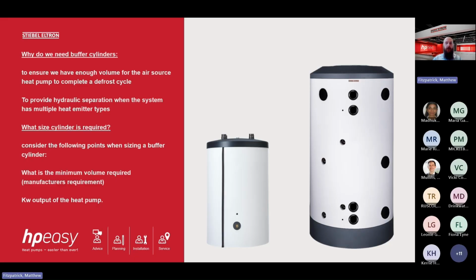So in the heart of winter, when it's very cold and very humid and the air source heat pump is extracting the energy from the air, it can pull the intake air exceptionally low to 0, -1 temperatures, which means any water droplets on the evaporator can freeze, and the heat pump runs in reverse to thaw out the evaporator. If we do not or cannot achieve sufficient system volume to complete a defrost cycle, we then need to have a buffer cylinder. Now, in some cases, defrost cycles can occur once or twice an hour, and with some systems can take up to 80 litres away from the heating system, which is a large amount.